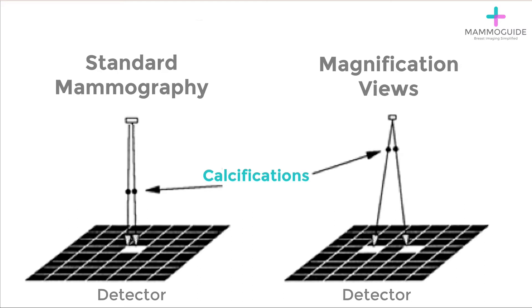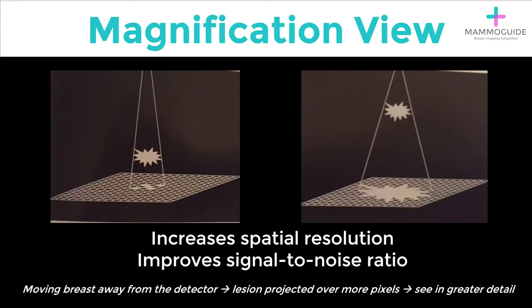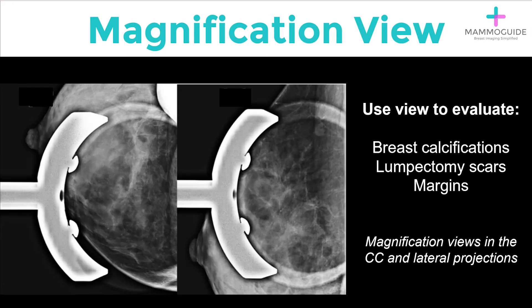This allows the abnormality to be spread out over a greater number of pixels, leading to increased detail. This increases the spatial resolution and also improves signal-to-noise ratio. Moving the breast away from the detector, the lesion projects over more pixels — you can see it in greater detail. Magnification views are used primarily to evaluate breast calcifications.